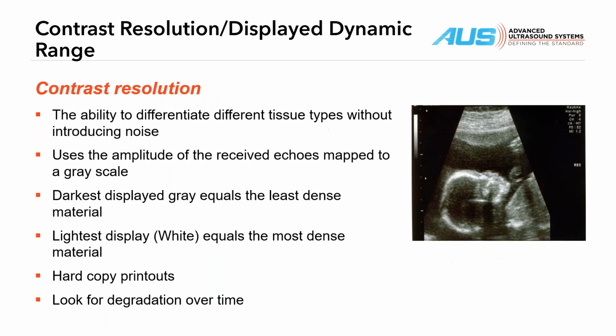Contrast resolution, different tissue types. Again, that means different densities. Using the amplitude of the received echoes mapped to a grayscale. So what we're talking about is, this is clearly muscle tissue, probably the abdominal wall right here, and you map the density of this structure to the grayscale right here. So it falls in this area somewhere, and that's an indication of the density of this object. This is not very dense right in this area. It's mapped to the darker part of the grayscale because it's not very dense. And you have the baby's forehead here, a bone structure, very dense, a huge echo, and it's mapped towards the white portion of the grayscale. Again, you want to make sure that you evaluate the 6 objects on your phantom and use that to watch for degradation over time.